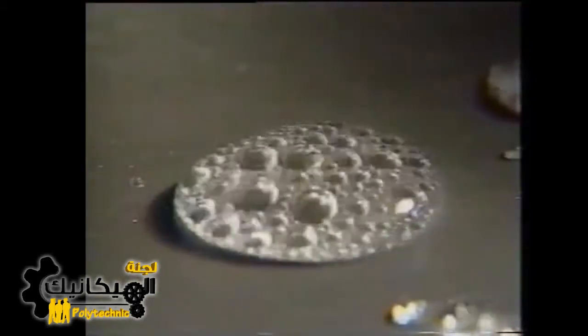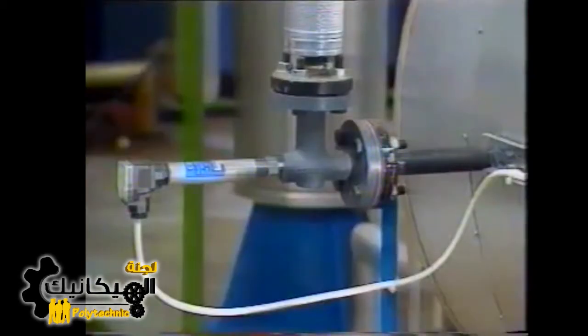Water contains chemical salts in solution called dissolved solids. These cannot be converted to steam. So when water is boiled, they remain behind and form a residue. This process happens continuously whenever a boiler is producing steam. And without some form of control, the concentration of dissolved solids would rise to an unacceptable level, the consequences of which can be seen in the following demonstration.